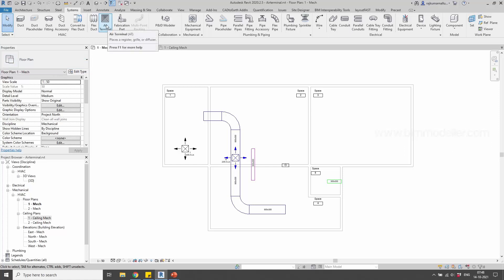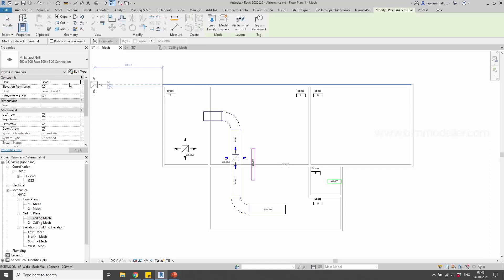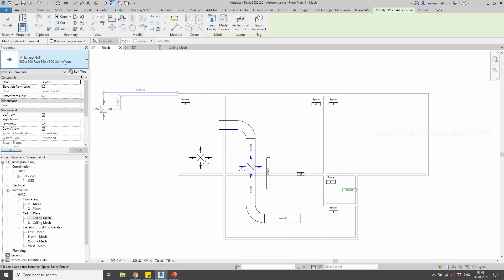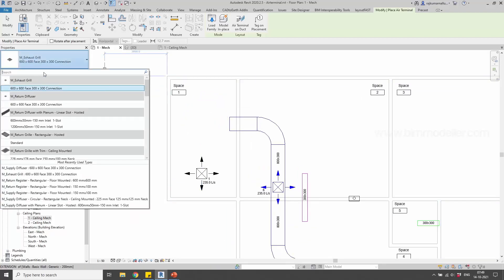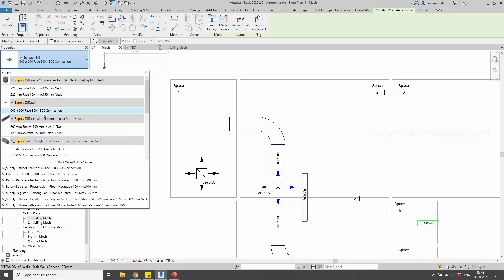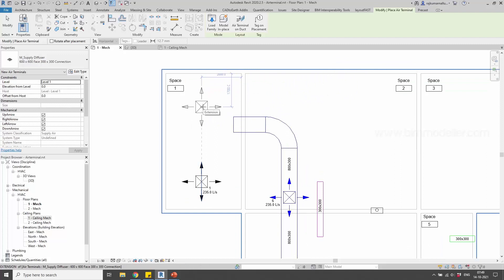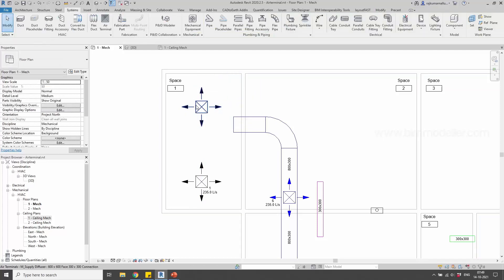The air terminal option is available in the System tab. Whenever you use a system default template and take the air terminal, by default it will be at Level 1 — the current level you are in — at elevation 0. Most of us make the mistake of placing it at 0 level. I'm looking for a supply diffuser, and if I take the supply diffuser, I can place it wherever I need. Just click — it will be placed, as simple as that.